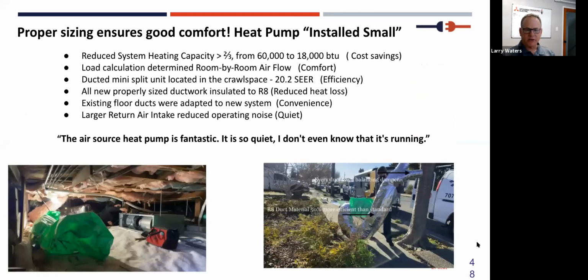Proper sizing—I can't emphasize this enough. If you're talking to an HVAC contractor and they aren't doing a real load calculation on your house, stop the conversation right away and call one of us that will. It ensures good comfort and helps us install small. You wouldn't believe how little heating and cooling capacity a house in the Bay Area really needs. For her system, we reduced the capacity two-thirds, from 60,000 down to 18,000 BTU.